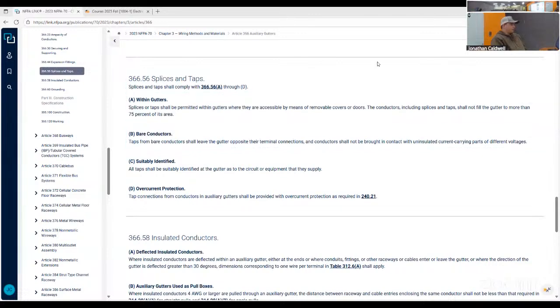Taps from bare conductors shall leave the gutter opposite from their terminal connections, and conductors shall not be brought in contact with uninsulated current carrying parts of different voltages. So that goes for bus duct mostly, because bus duct is uninsulated bus bar. It is literally bare copper inside those. All taps shall be suitably identified at the gutter as to the circuit or equipment they supply.